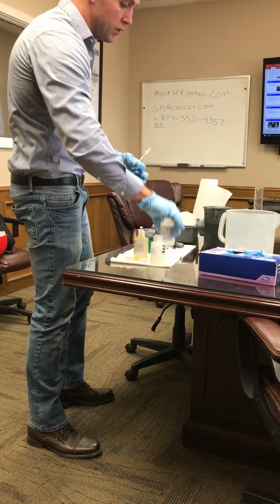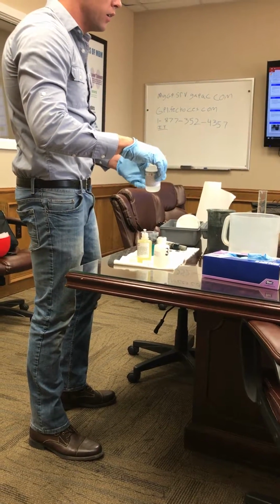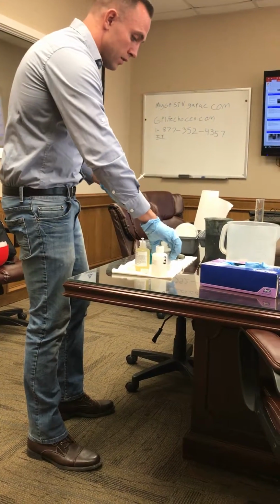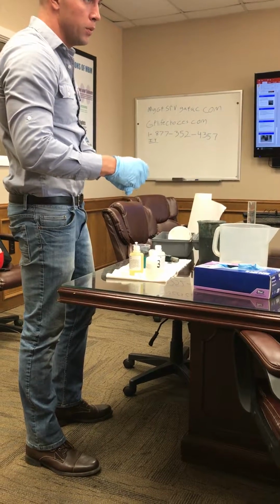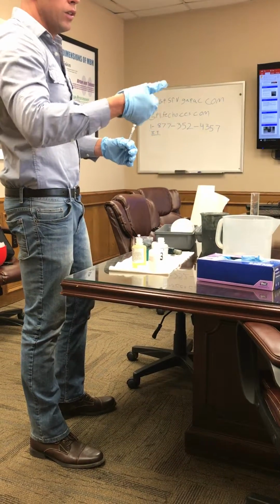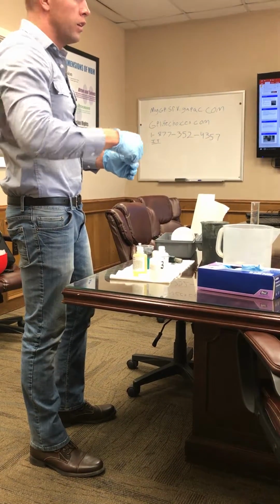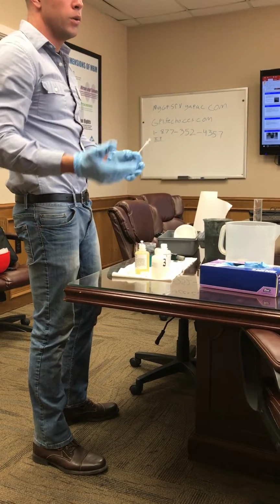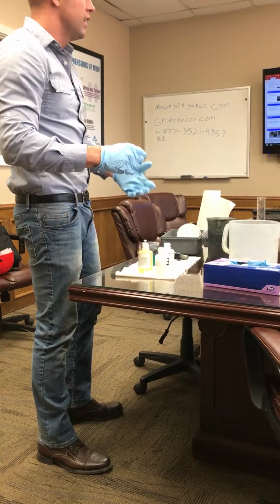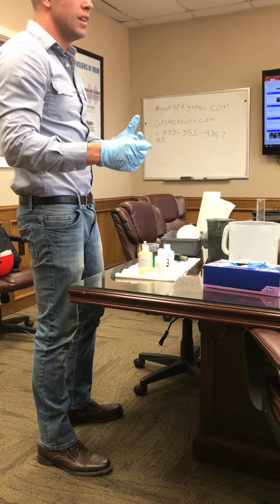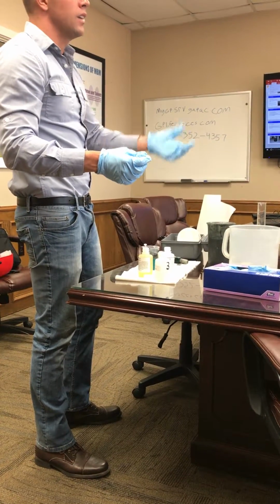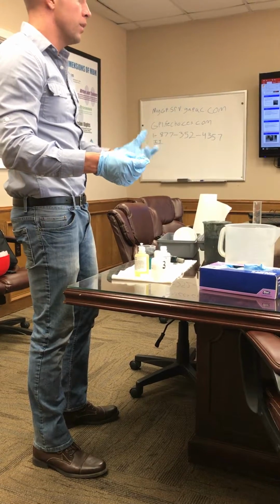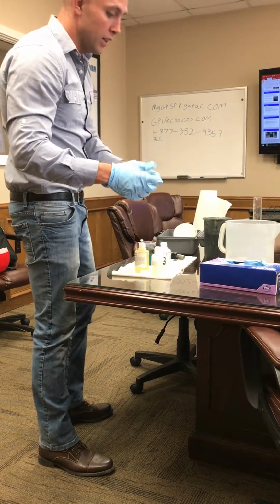And all the caustic does is just adjust your pH. It doesn't do anything else. It brings the pH up. Be careful with that, because I've seen people at some plants leave the caustic switch in manual and walk off to do another task, and they come back and they've pumped the whole tote of caustic into that tank. That brings the pH up, I've seen it at a 12 to a 14. Then they have to call a hazardous waste truck to come out and pump it, and that's going to cost you guys a lot of money.